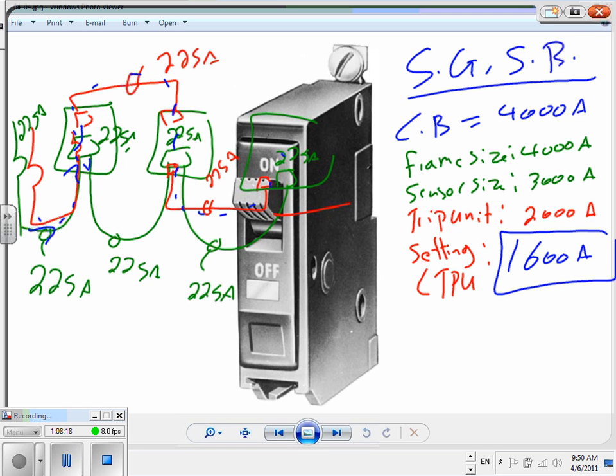Now, my question for you, Jim, my friend, everybody else: when I size cable for this circuit breaker, which amps should I use? You need to size cable. Which amp should you use to size? Should I use the 4,000, the 3,000, the 2,000, or the 1,600? When it comes to the trip, we size cables exactly based on the setting, guys.